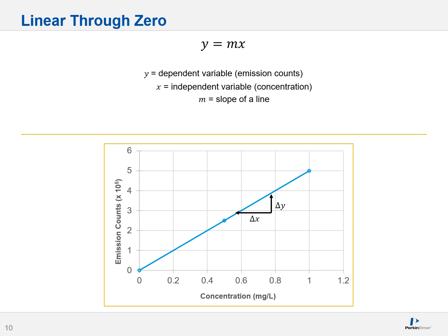Why would one use this curve? Yes, inherently they are not as accurate as simple linear curves. You are forcing a curve. But sometimes you don't have a choice. In certain applications, your background or your bogus counts may be so high that your y-intercept may be completely unusable, at low levels anyway.